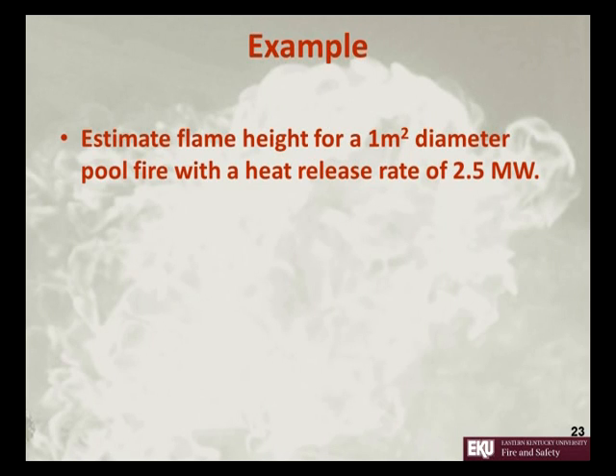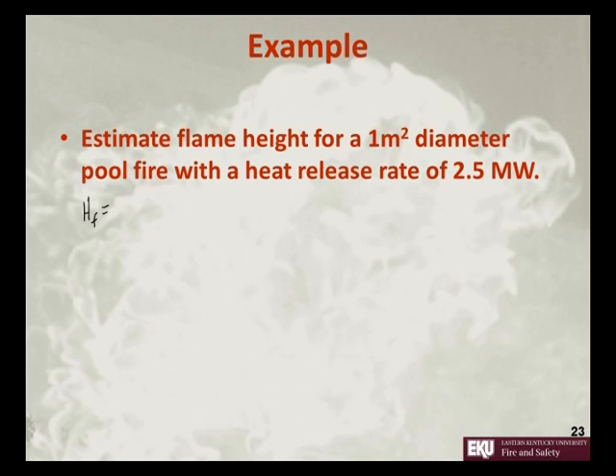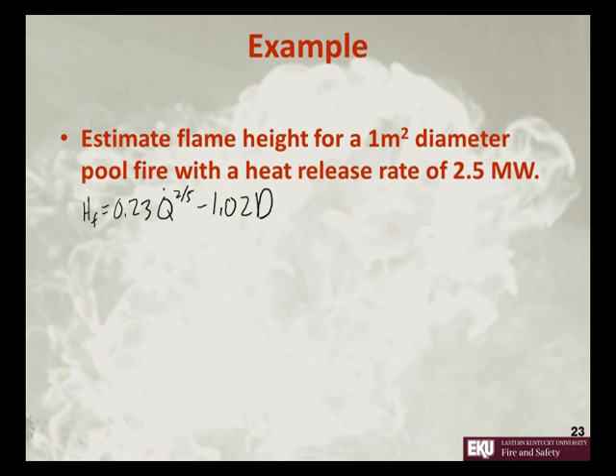Alright, so let's do an example. We're going to estimate the flame height for a 1 meter squared diameter pool fire with a heat release rate of 2.5 megawatts. The height of the flame is equal to 0.23 times the heat release rate to the 2/5 power minus 1.02 times the diameter.